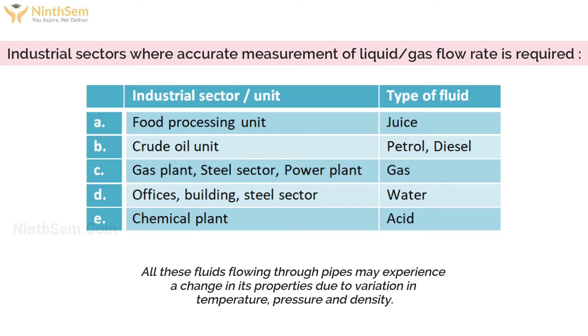So all these fluids or gases flowing inside the pipe have certain changes due to the variation of temperature and pressure. To overcome such problems, the French scientist Gaspard Gustave de Coriolis invented the Coriolis force, that is an internal force that acts on objects which are in motion. Now this Coriolis force causes deflection on the tube inside which the flow is going on. This force is superimposed on top of the vibratory motion of the tube. Now the frequency of vibration has a change in phase shift in the form of change in time, which measures the flow rate. Now I will explain how the mass is directly measured in the Coriolis mass flow meter.